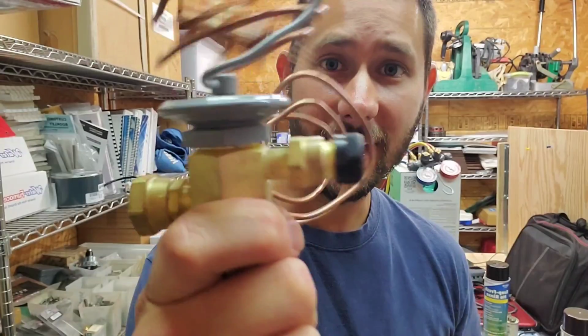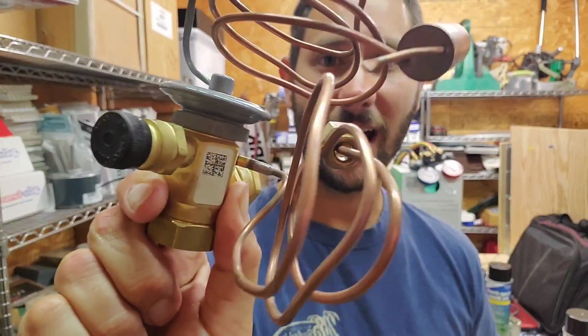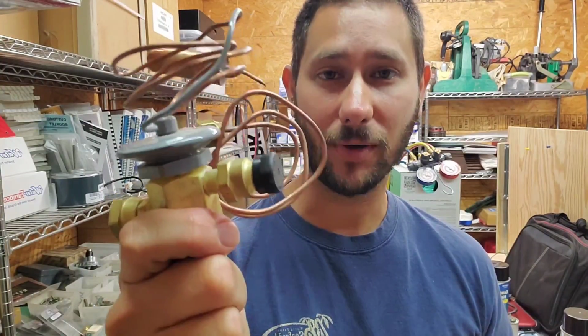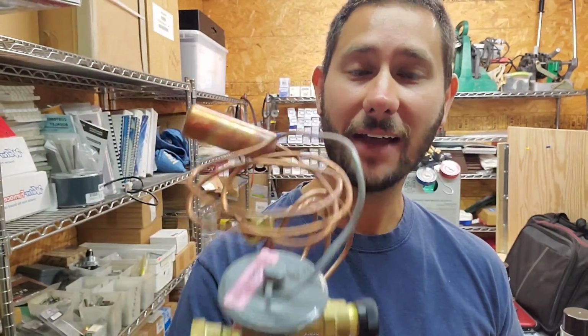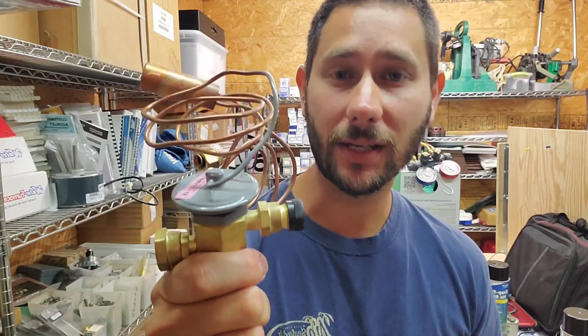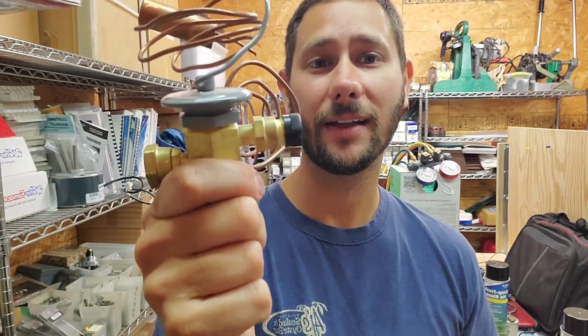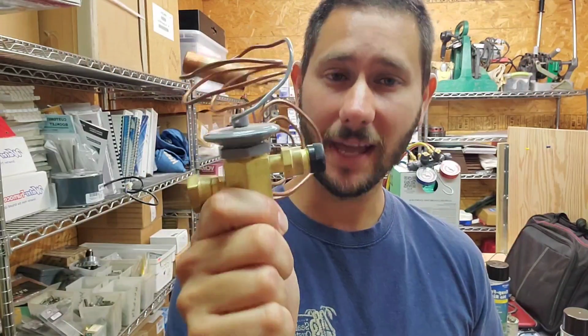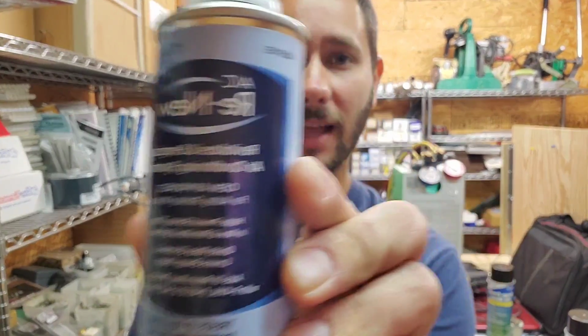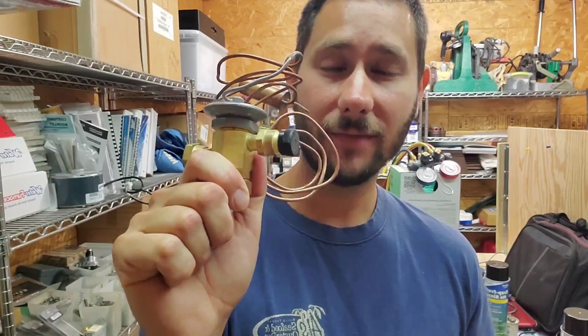Let's move on. This is a TXV, a thermostatic expansion valve. It's a metering device that's used in air conditioning systems that regulates the amount of refrigerant that goes inside of the evaporator coil. It has a bulb, a diaphragm, a seat, and it's supposed to open and close, but sometimes it can get stuck. And usually I either have to replace this TXV or I have to add some type of additive like AC Renew to help to aid in this stuck TXV.